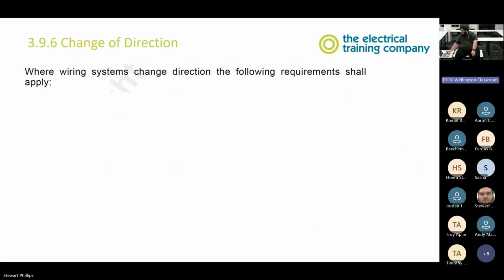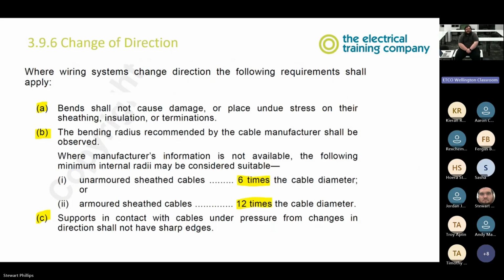Where wiring systems change direction, bends shall not cause damage or place undue stress on their sheathing, insulation, or terminations. What does this mean? Undue stress. Why are we worried about undue stress on their sheathing, insulation, or termination? It can weaken the insulation of the conductor. More heat, yeah. Can break the conductor, yeah. Internal damage, yeah. So everyone's worrying about the conductor.